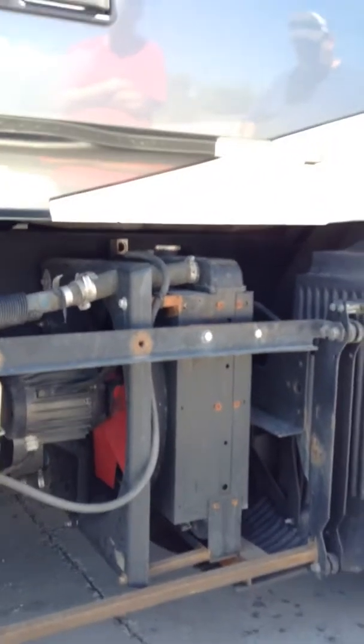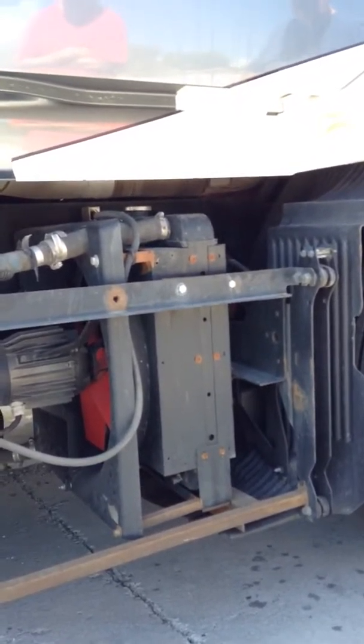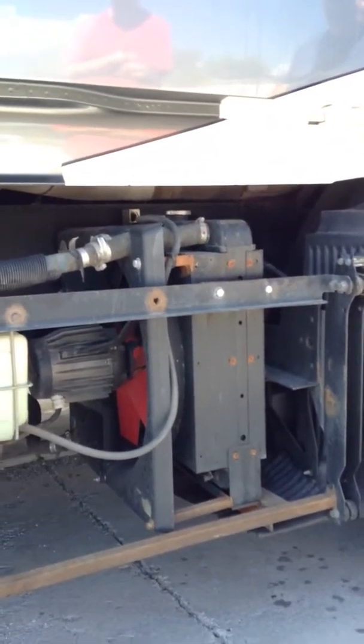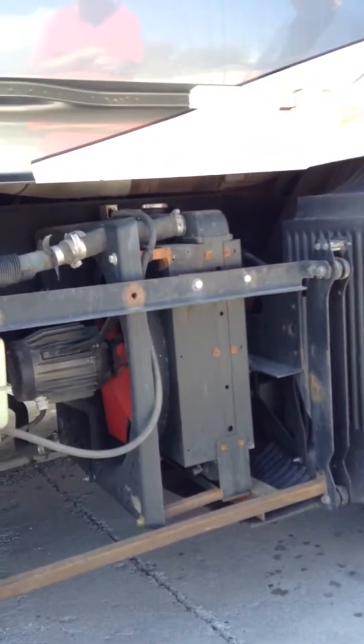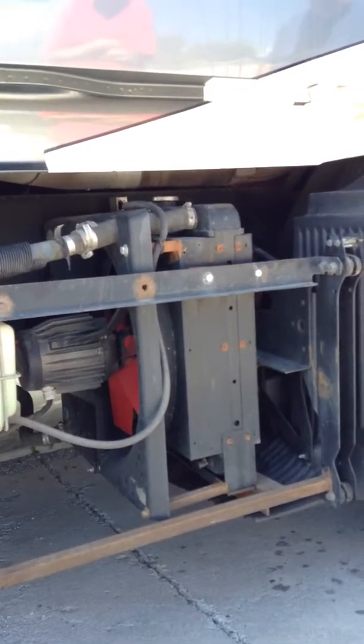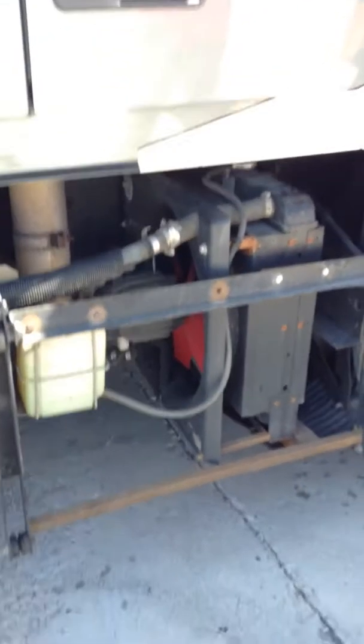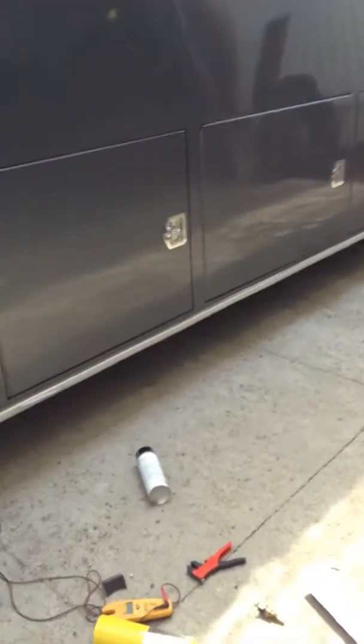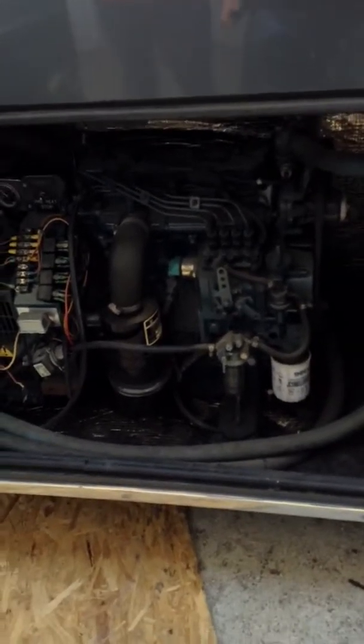If you're fighting the water temperature and all of the fans are running and the water pump is also running, you could actually remove this side skirt and put it in one of the storage bays in the back under some extreme heat conditions. If the fan that changes the air in the generator compartment itself happened to fail, you could very carefully use a block of wood or plastic or something possibly and tie this door to where it was open 3 or 4 inches, and that would also get rid of the heat inside that box. Those may be 2 workarounds on the system.